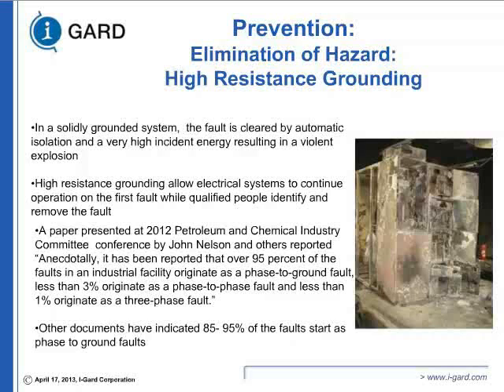The risk. Other documents I have also mentioned: one document was EPRI, which covers utility industries, saying 85 to 95% of faults start as phase-to-ground faults. So it stands to reason, if we can eliminate the initiating condition, we won't have that problem. This practice was initiated in the 1960s by industrials purely for continuation of power, because you don't want to shut down the continuous process industry.